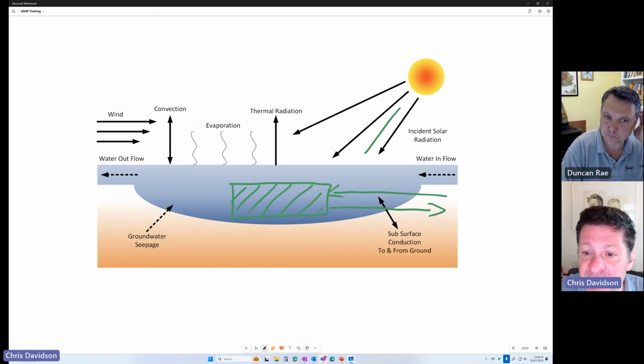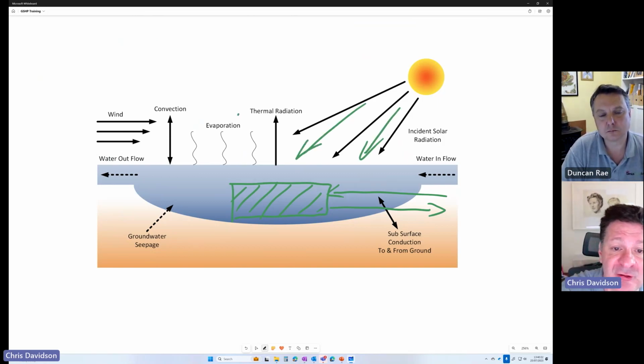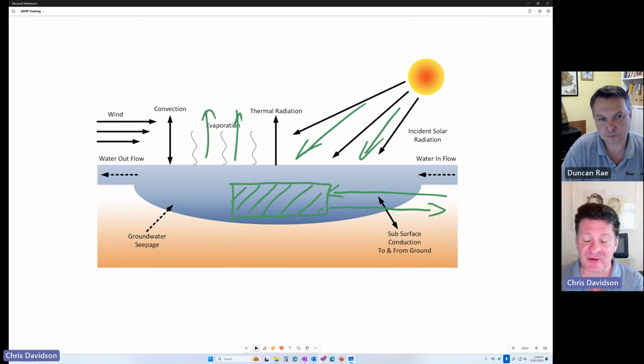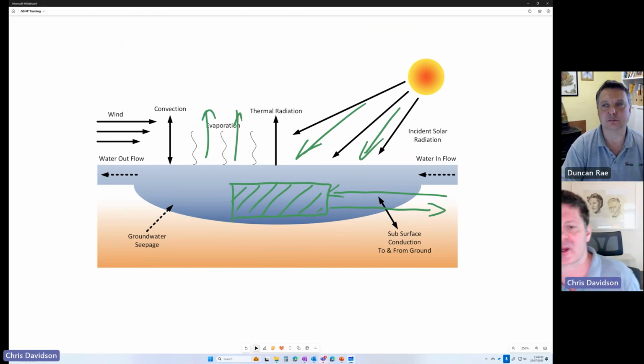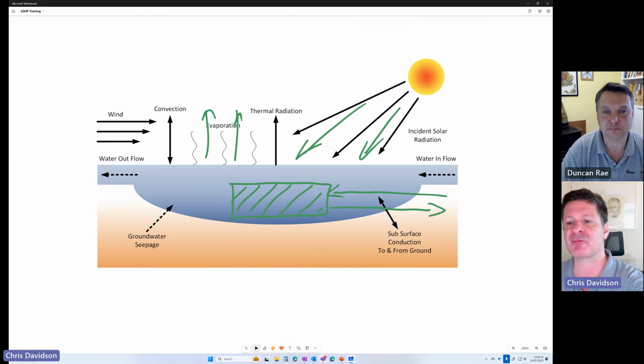The main gains are solar gains, and the main losses are actually via evaporation. So these systems can be very, very powerful, particularly when we start to look at new build multi-residential, new build business parks, things like that, to include an element of surface water for landscaping, for maybe sustainable drainage as well, and double the utilization of that by doing heating and cooling as well. It can be incredibly attractive and can be a lot less expensive than boreholes, for example. So that's the closed loop of fluid circulating. So it's the same fluid circulating round and round.